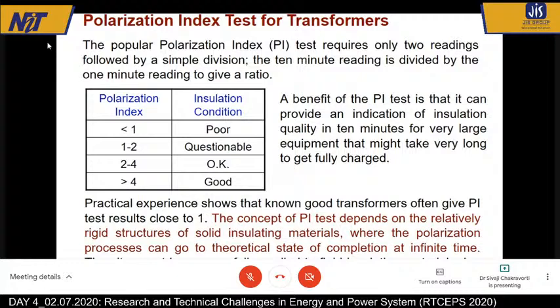Typically, when you connect the Megger to an insulation or any equipment, a certain DC voltage is applied to the equipment. It could be 500 volts to 5000 volts. When a voltage is applied, the insulation gets charged, and the charging current gradually decreases. It measures the voltage applied and the current and then divides to get the insulation resistance. So it is quite expected that the current at 1 minute will be higher and at 10 minutes will be lower. So if we divide the 10-minute insulation value by the 1-minute insulation value, it will be greater than 1.